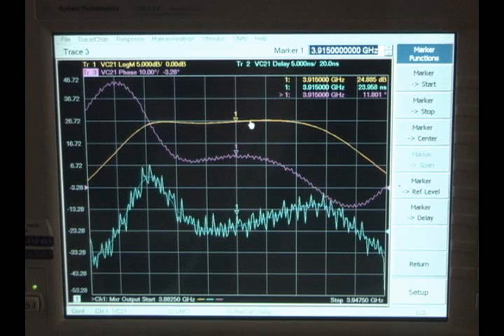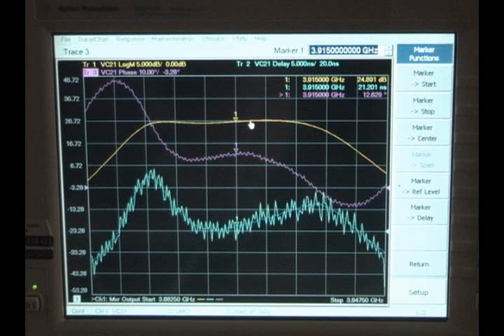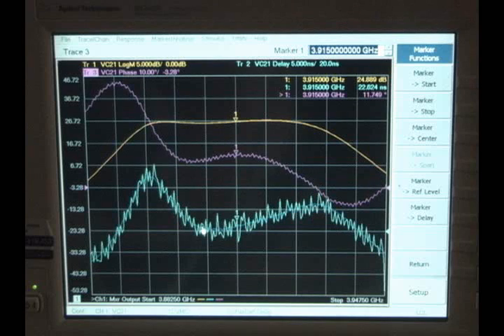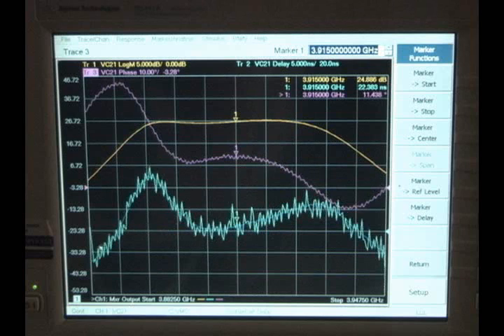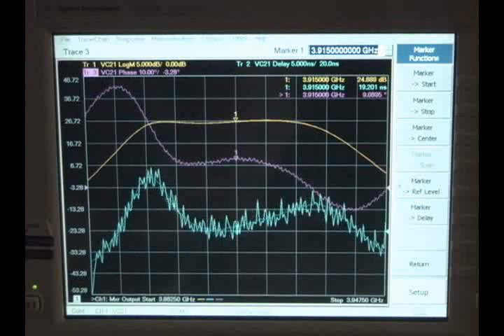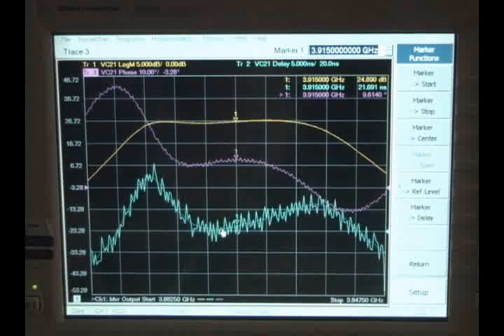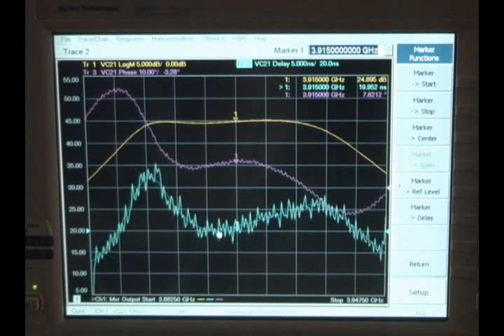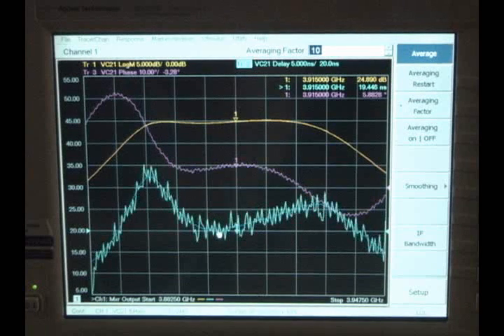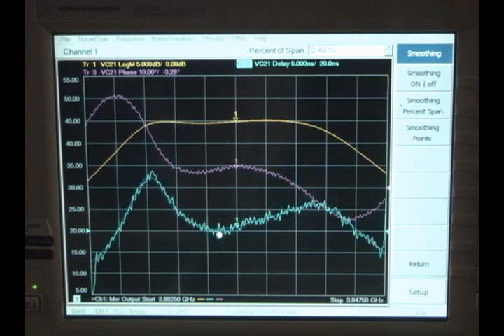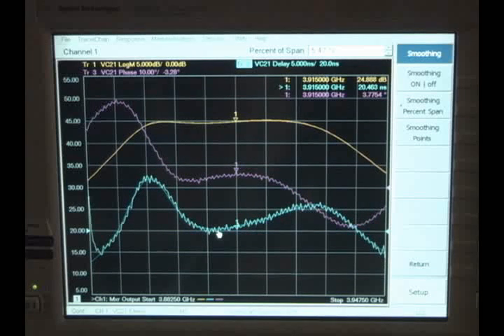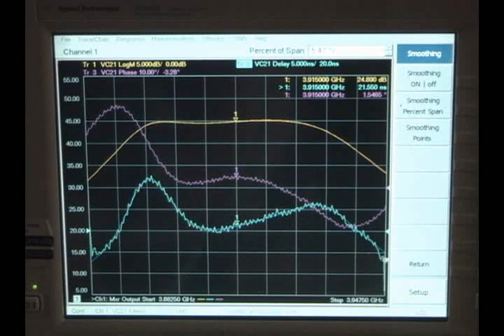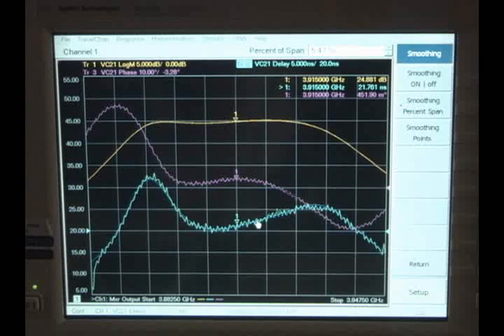But notice that the average of the signal is still exactly where it was before, shown by the darker blue trace. So with a little more averaging, more smoothing and a little bit of averaging, we can clean up that trace and still make a good measurement. I'll just turn on some more smoothing here. I'll bump it up to about four and a half percent, actually make it say five and a half percent. And you can see now that we're very close back to our original measurement. And if we turned on averaging, we could clean up the noise even further.